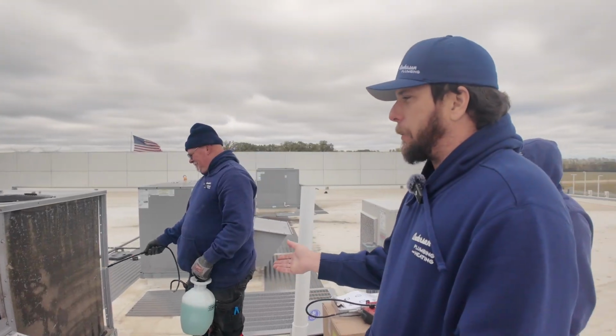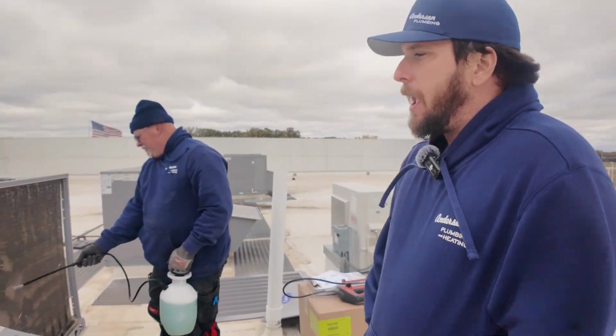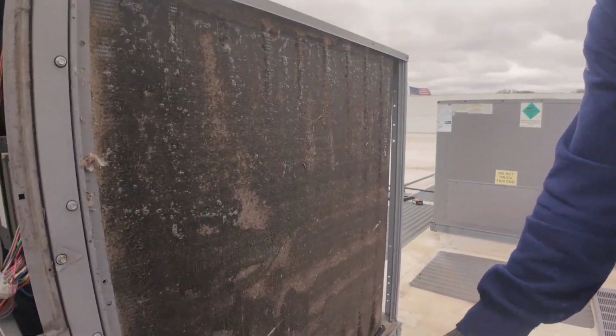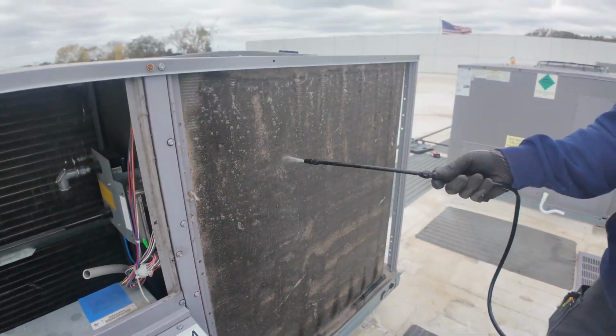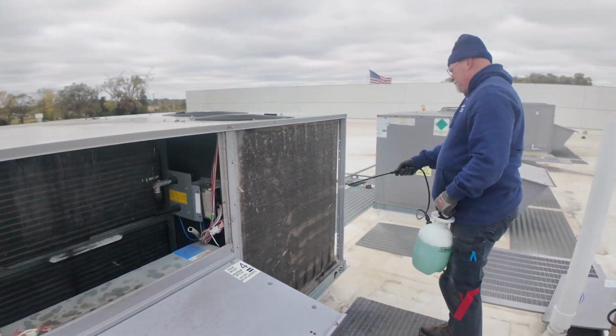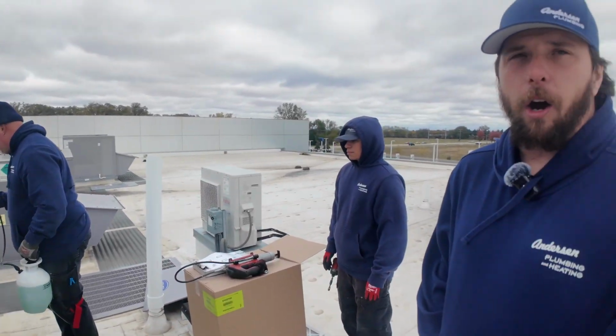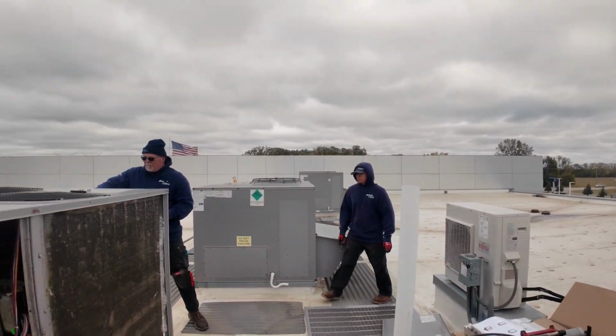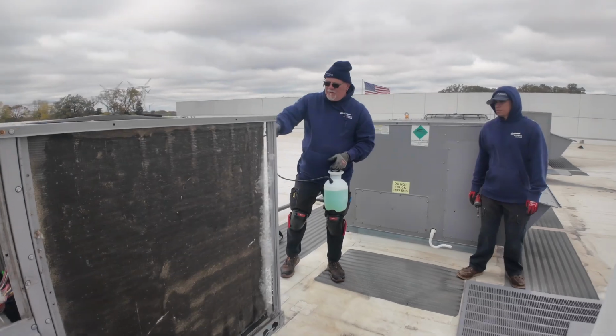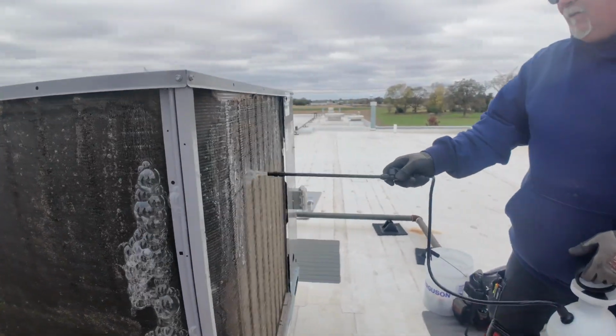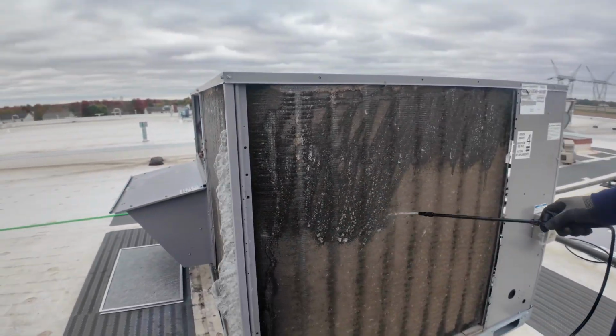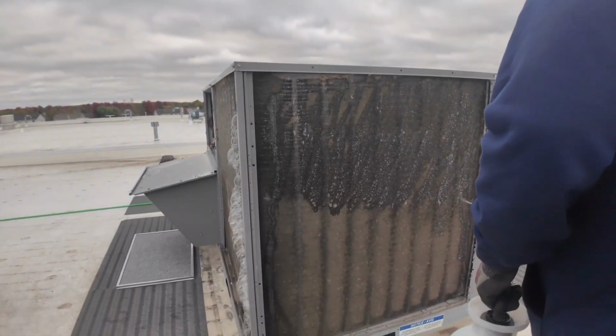So what Cory's doing is he's spraying down the coils with coil cleaner. It's safe to be used on coils because coils are aluminum. That way they won't corrode, give us problems in the future. You know, if you use any chemicals that are too harsh, you can actually damage the coils. So he's going to spray the coils down, let them soak for a couple minutes, both the evaporator coil and the condensing coil. And it also is a bubble machine. But we're going to spray them down, let them sit for a couple minutes, and then we'll get the giant pressure washer up here and get them sprayed off.